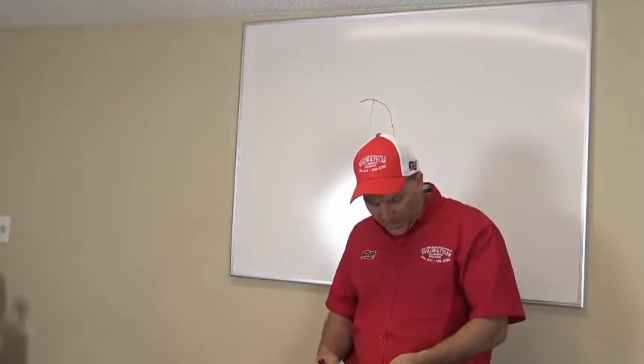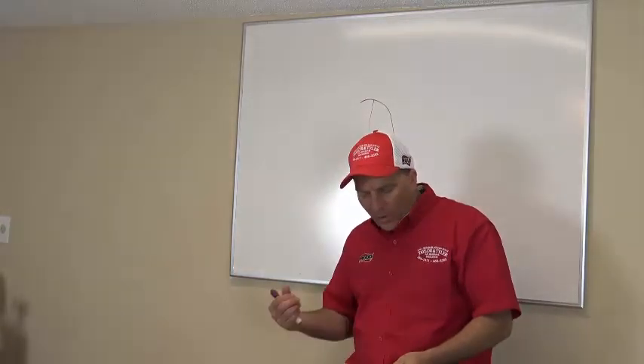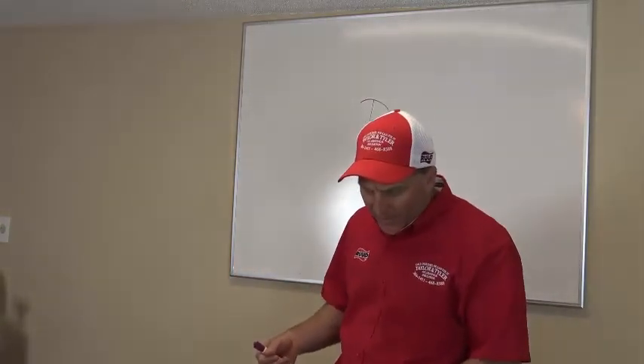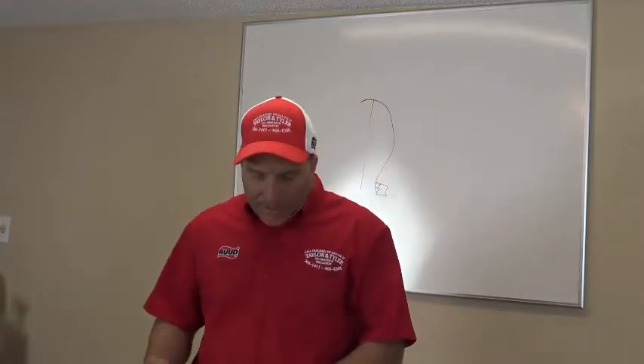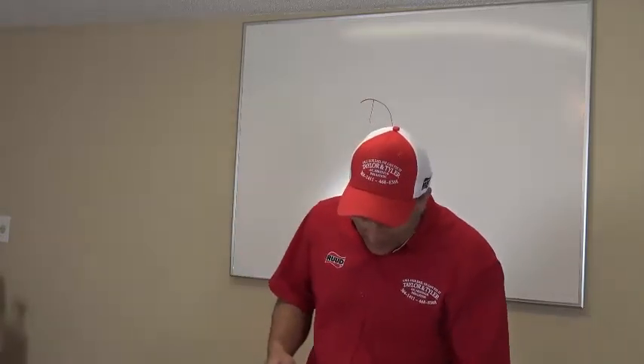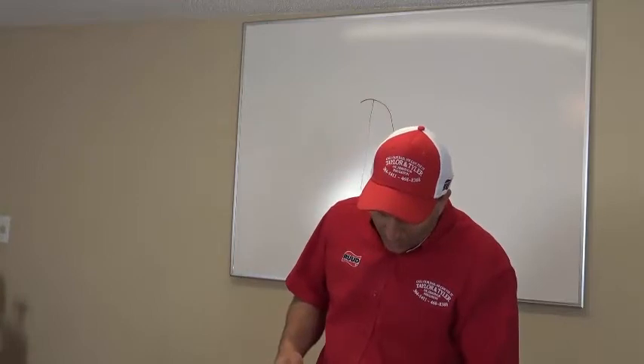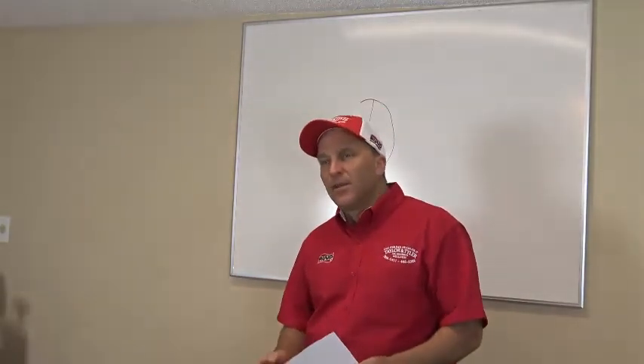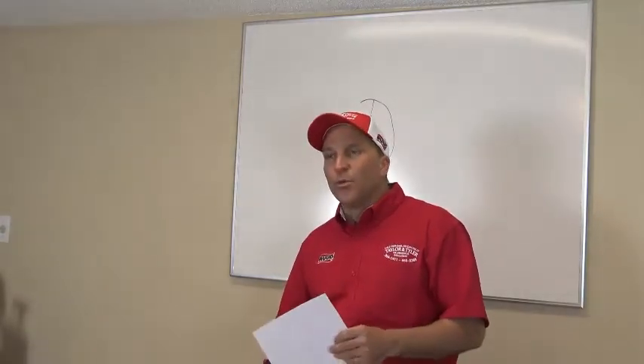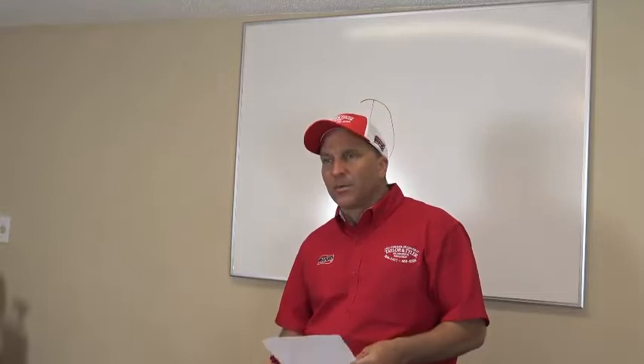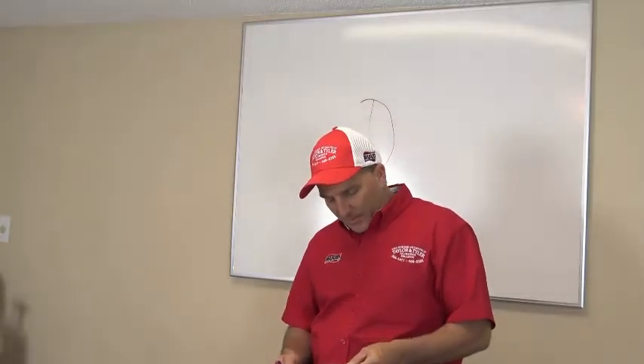Go up to the top now, which you got your coil. I want to know if it's R22 or 410A. Then you go to your air leaks. Air leaks are going to be none, small, or major. Well, if you don't go check the duct system and the supply plenum and all that kind of stuff, how are you going to know that? So you got to get up there and go do a little work, don't you? Don't assume. Spell out assume, guys. Yes, you and me. Okay.